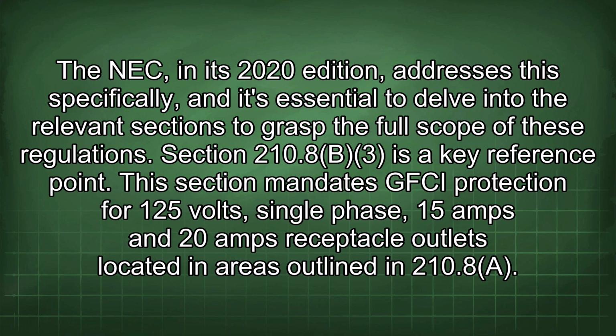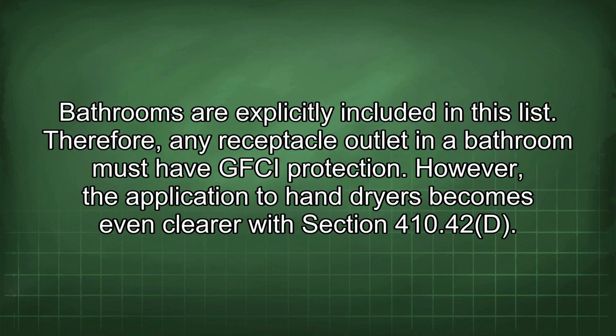This section mandates GFCI protection for 125 volts, single-phase, 15 amps and 20 amps receptacle outlets located in areas outlined in 210.8(A). Bathrooms are explicitly included in this list. Therefore, any receptacle outlet in a bathroom must have GFCI protection. However, the application to hand dryers becomes even clearer with Section 410.42(D).